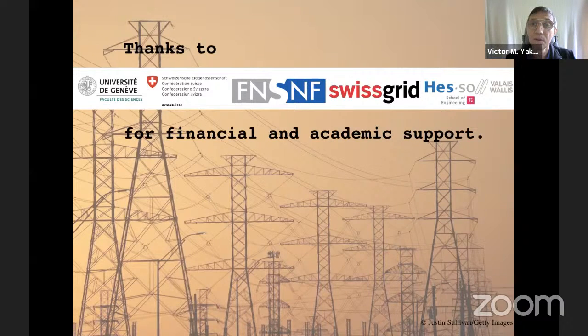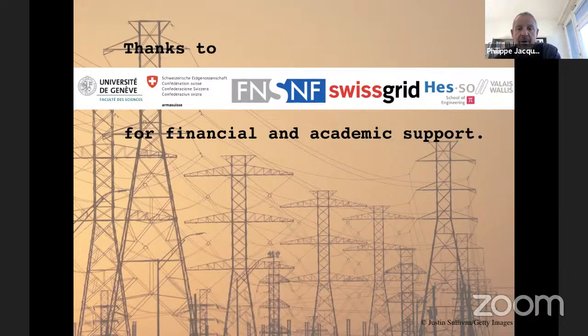There was an event where the frequency changed too fast at some substation connected to one of those lines. That's what's called ROCOF, rate of change of frequency. If it exceeds something like 0.5 hertz per second, or a bit more depending on location, the line is opened automatically as a protective measure.